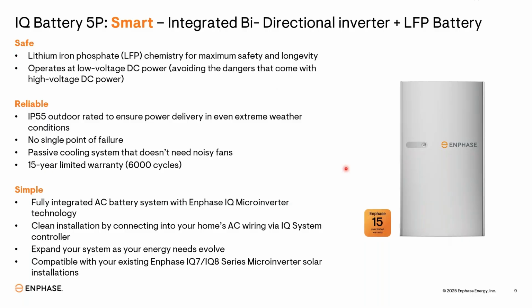Talking about the warranty, it comes with a 15-year limited warranty or 6,000 cycles. If you count one cycle daily, it goes for more than 15 years. It's a simple, fully integrated battery system with Enphase microinverters. Everything you need is inside these batteries. No need for extra wires. You get 230-volt AC from these batteries. Very neat and clean installation. Once you start your installation, within 4 to 5 hours you can leave the site with the installation of your batteries and commissioning complete.